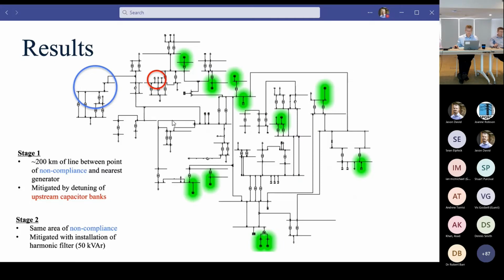So looking at potential ways to mitigate these levels, we found that the quickest, easiest and simplest way was to just detune the upstream capacitor banks. We were able to do that quite quickly, and then move on to stage two and applied another 500 MVA of connections, all with harmonic sources, punching harmonic current into the network. Again, same area of non-compliance. This was the point at which the harmonic impedance was the highest for a number of harmonic orders.